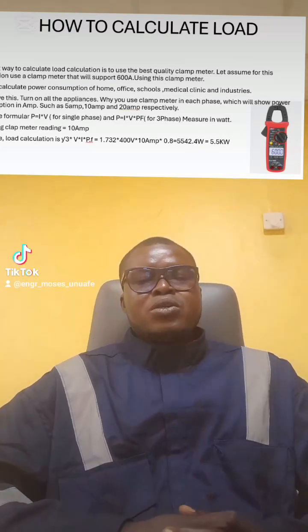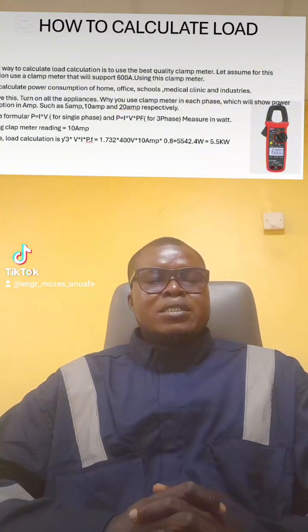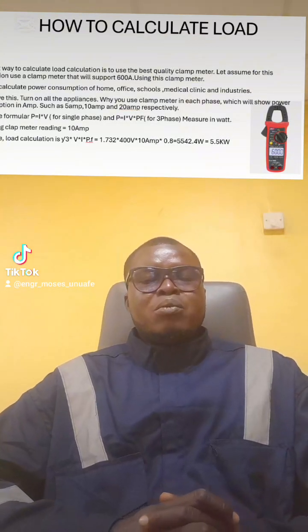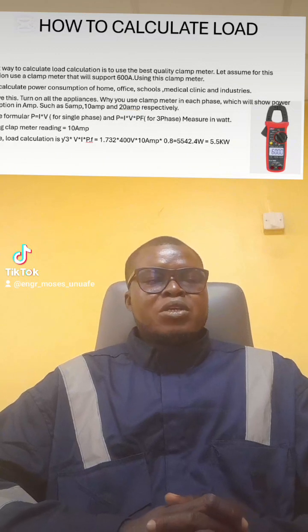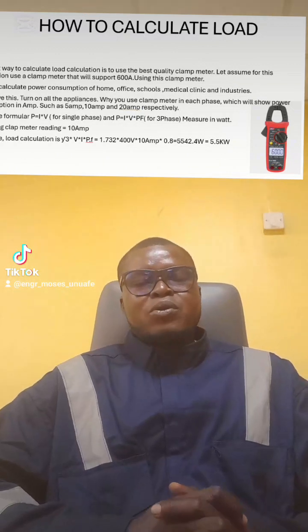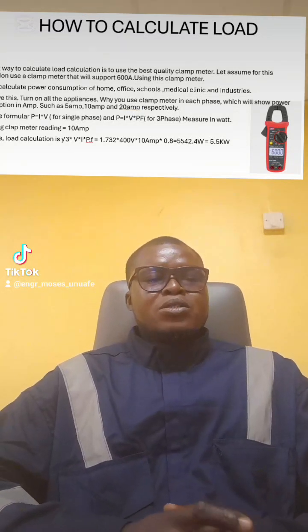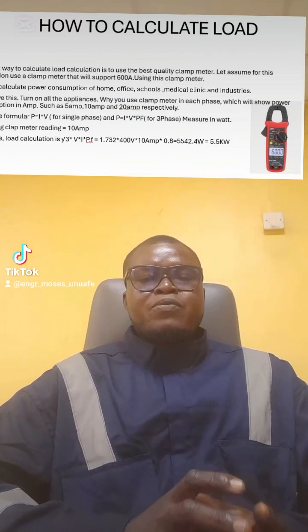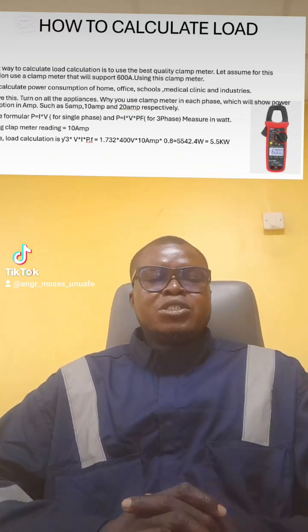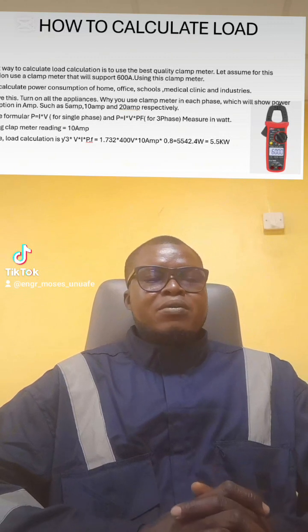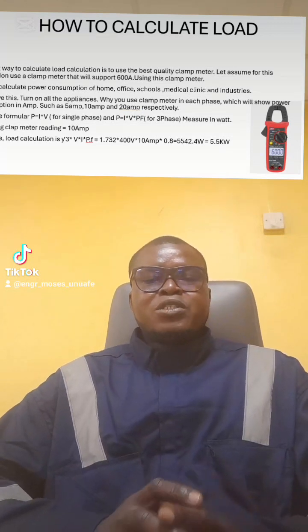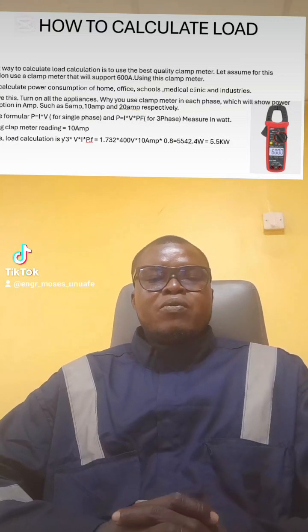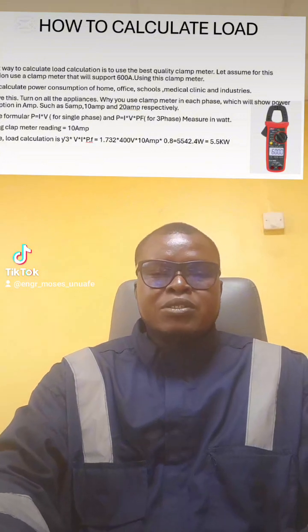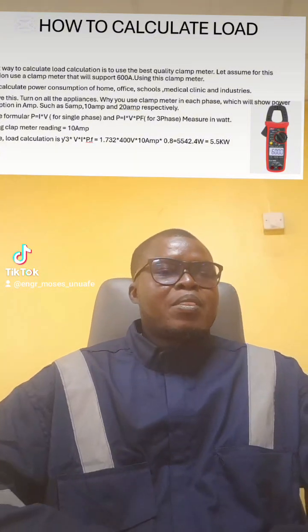Power equals current times voltage multiplied by root 3 times the power factor. On substituting this, knowing fully well that our voltage is 400 volts, it is going to give us what? 5.5 kilowatts after multiplication, as you can rightly see.